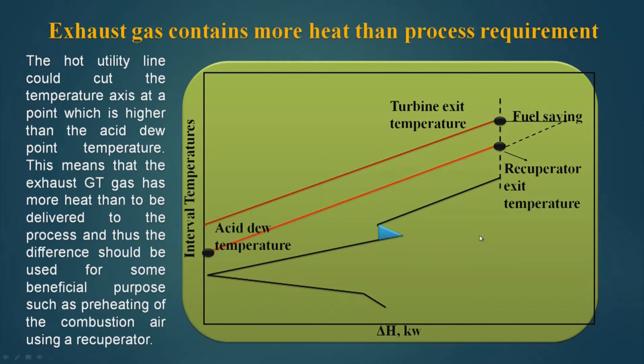The hot utility line could cut the temperature axis at a point higher than the acid dew point temperature, as we see in the picture. This means the exhaust gas has more heat than to be delivered to the process, and thus the difference should be used for preheating of the combustion air using the recuperator. Basically, using the recuperator we are resizing it and making the matching better.